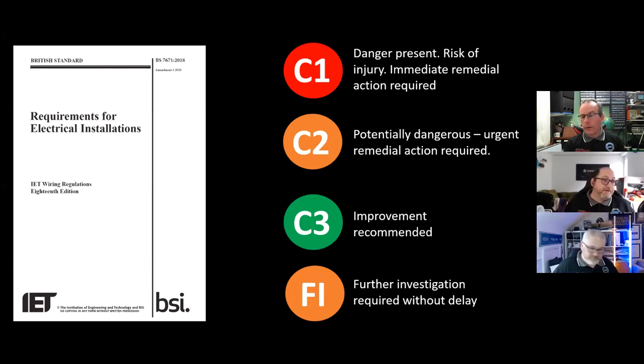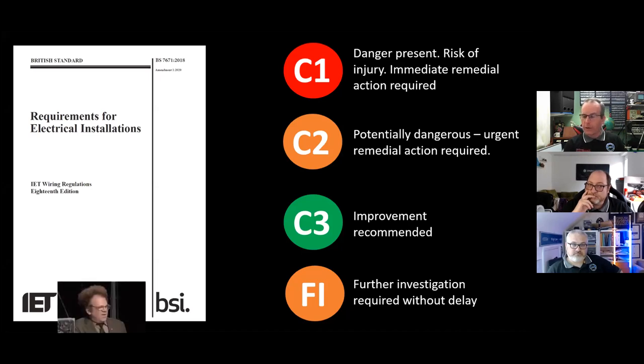Yeah, I think the point with all of these is that whatever code you're going to put down, it's not just going to be, oh, here's a code, that's the end of it. You're going to have to put it's C whatever or FI because, and then an explanation as to what actually the problem is and what further actions may or may not be needed. Because if you just stick down a code, it's pretty meaningless just on its own. So yeah, they all need context and additional information.